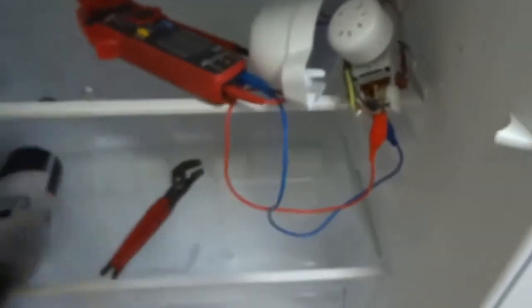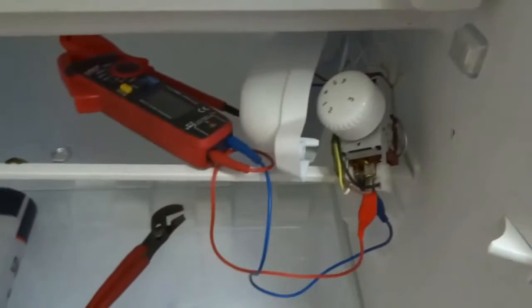So that's just really controlled inside, and basically it's just an on and off switch. You're testing there, so off, no power going to the compressor. On, power should go to the compressor now. So this is a perfectly good working thermostat.